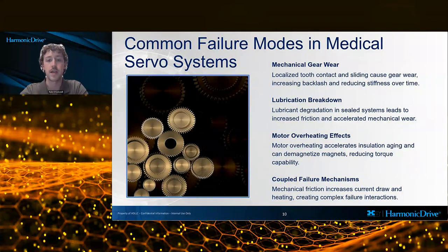Additionally, interactions between mechanical and electrical subsystems can create coupled failure mechanisms, such as increased friction leading to higher current draw and additional heating in your system. In medical systems, these gradual degradation modes are particularly problematic because they can lead to subtle performance drift rather than abrupt failure. Designing with a clear understanding of these failure modes and how they happen allows engineers to incorporate appropriate margins and monitoring strategies, as well as architectural choices like strain wave gears that inherently reduce the likelihood and impact of wear-related degradation.